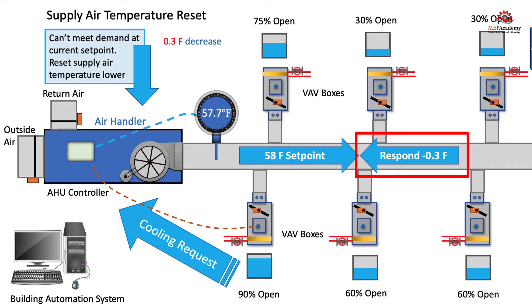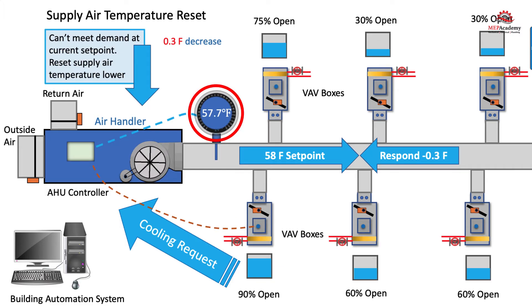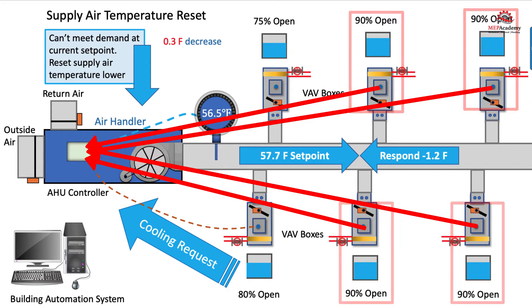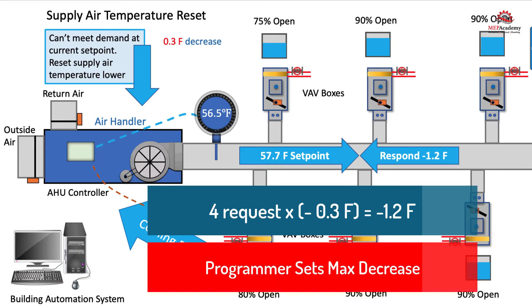For example, by 0.3 degrees Fahrenheit. If the temperature was trimmed up to 58 degrees before a request was made, the request would decrease the supply air temperature to 57.7 degrees Fahrenheit. If multiple VAV boxes send requests at the same time, the value is multiplied by the number of requests. If four VAV boxes sent a request for more cooling, the supply air temperature could be reset by 4 times 0.3 degrees Fahrenheit, for a total of 1.2 degrees decrease. The controls programmer will limit how much the supply air temperature can be decreased at any one time, no matter how many requests are sent, allowing system stability.